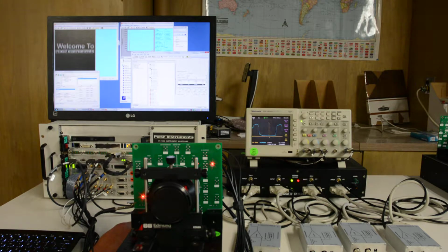And I can control the filtering. I have a 10 megahertz 3 dB filter on the signal right now. I can change this back to open. There's not much change on the video image, but you can see the waveform on the monitor points have some overshoot.